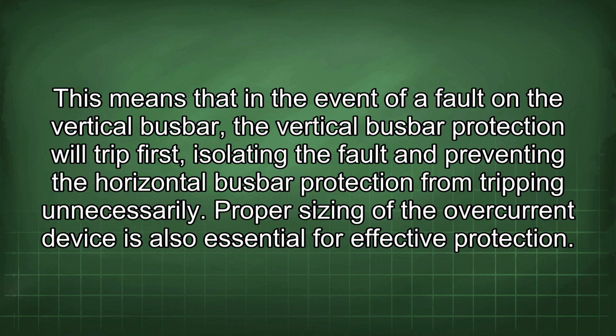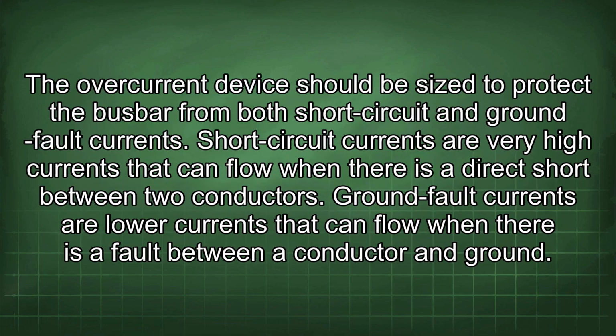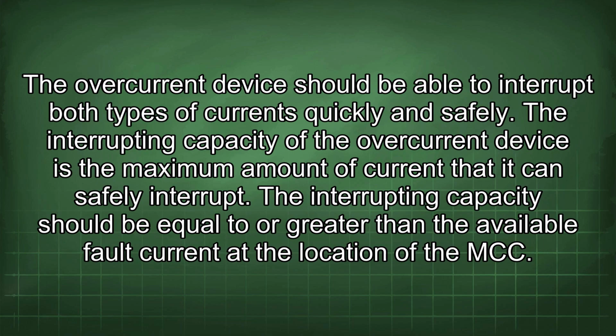Proper sizing of the overcurrent device is also essential for effective protection. The overcurrent device should be sized to protect the busbar from both short circuit and ground fault currents. Short circuit currents are very high currents that can flow when there is a direct short between two conductors. Ground fault currents are low currents that can flow when there is a fault between a conductor and ground. The overcurrent device should be able to interrupt both types of currents quickly and safely.